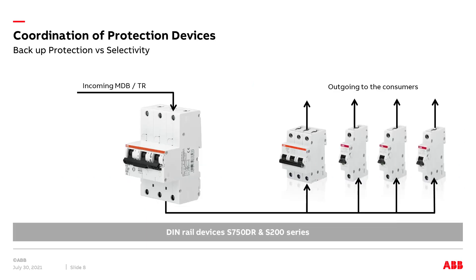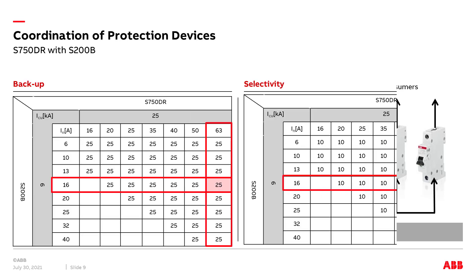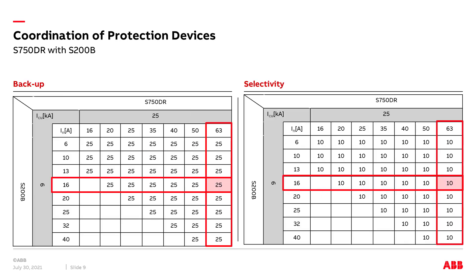In the last example, we will use an S750DR on the incoming side and the same MCB S200 on the outgoing side. Again, the incoming breaker is chosen at 63 amperes and the outgoing breakers at 16 amperes. The backup protection is a bit smaller at 25 kilo amperes compared to the other two examples. Due to the specific function of the S750DR, the selectivity level is 10 kilo amperes.